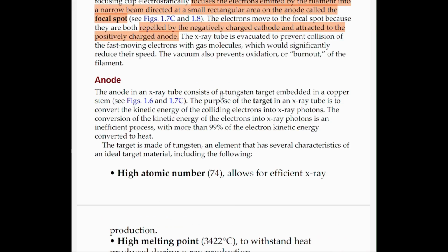So the anode consists of what? It consists of a tungsten target embedded in a copper stem. The purpose of the target in an X-ray tube is to convert the kinetic energy of the colliding electrons into X-ray photons. So that is the main work of the anode. The target is made of tungsten, very important, an element that has several characteristics of an ideal target material.